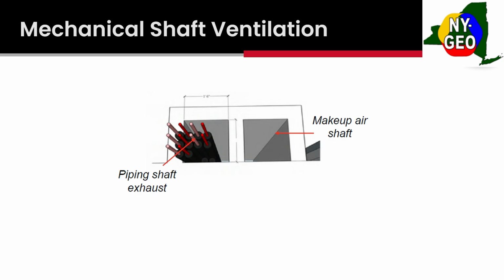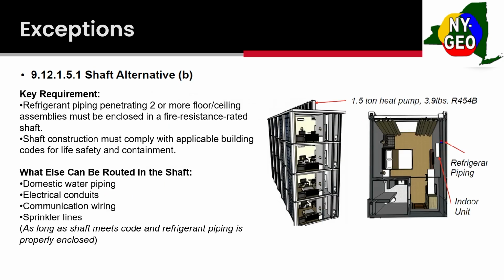So we talk about the exemption on the top floor. Again, you can route domestic water, electrical, communication, your sprinkler lines all through that same shaft. So you can design that shaft big enough just to run all your utilities through it, or design it small and just run your refrigerant lines through it. It's really up to you.